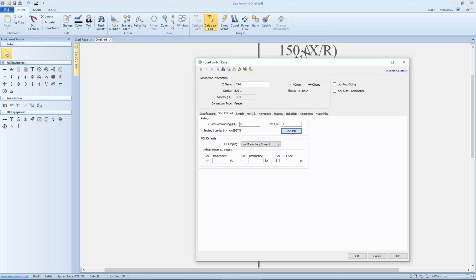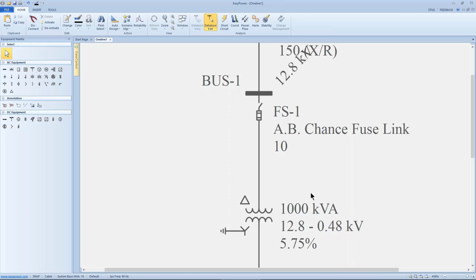The fact that this X over R test environment changed says, Jim, I found the part number you gave me. The manufacturer has a data sheet. He's tested it to an ANSI standard using symmetrical current and an X over R environment of 15. Now normally a protective device has an interrupt rating, but because this particular fuse does not even have a holder, it's just a piece of wire stretched across the switch, it doesn't have an interrupt rating, so we're not going to look at that right now.